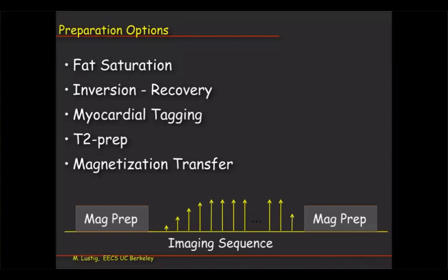Okay, that's one example that is very typical to do. Or you can leverage the T1 shortening of fat, the short T1 of fat, in order to do an inversion recovery type. And depending on the field, then you want to apply one or the other. For example, in low fields where the frequency between fat and water is actually not very far, then you'd want to maybe rely more on T1. But for higher field, it's very easy to separate between fat and water because they're so far apart in terms of the resonance frequencies, right? Because it's really field dependent. We're talking about ppm shifts, so it's really always with reference to the resonance frequency. So at 7T, I mean, we're talking about a kilohertz away, right? That's really, really far.